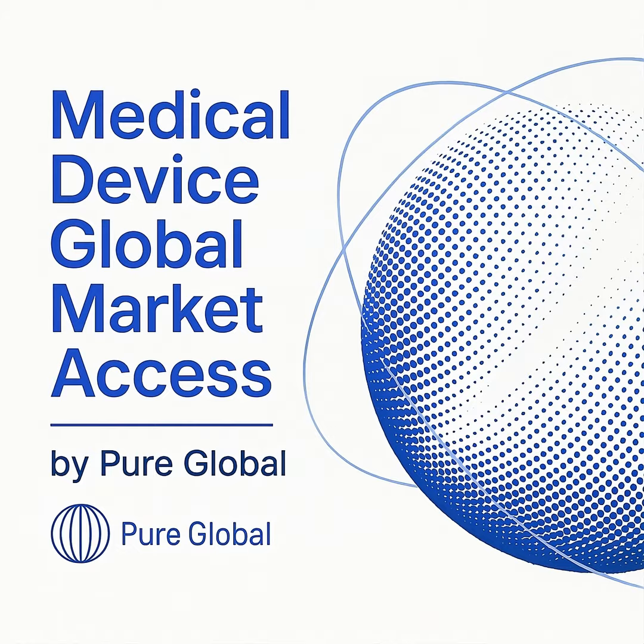The primary role of the in-country representative begins with product registration. They act as the formal point of contact with the national regulatory authorities, such as the FDA in the United States, a competent authority in an EU member state, or the TGA in Australia. The representative is responsible for submitting the registration dossier and managing communications with the agency throughout the review process.